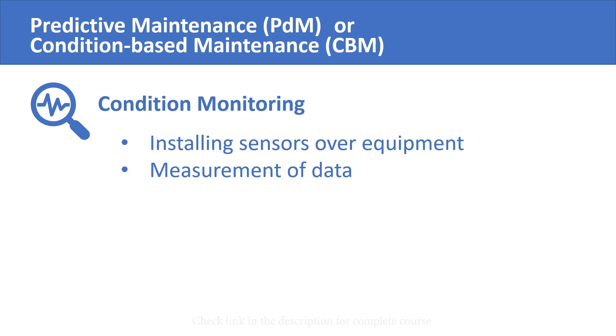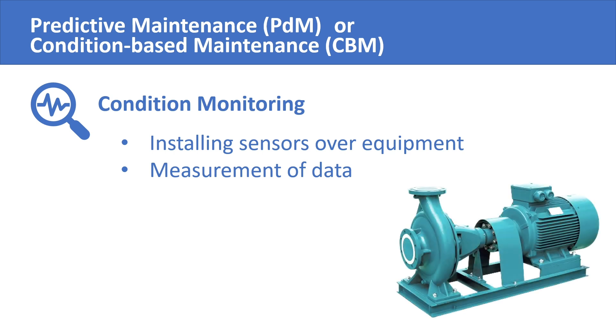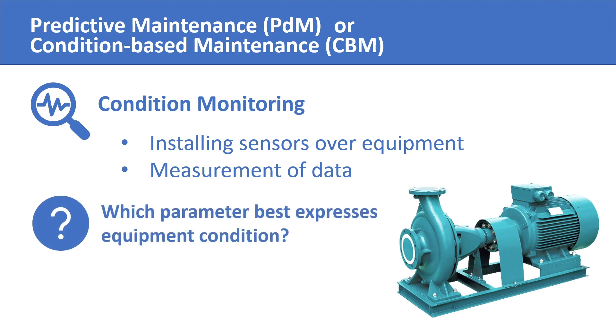For example, if you want to apply condition monitoring over an industrial pump in order to do predictive maintenance on it, you would ask yourself which operating parameter best expresses good health of the pump. In the case of the pump, which is a rotary equipment, its vibrations are a very good measure of its condition. A pump in good condition will have low and stable vibrations, and as any component inside the pump degrades, it will generally raise pump vibrations.